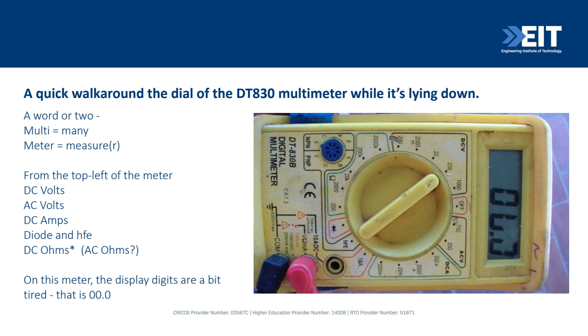While we're still on this one, if you look at the actual display here, you'd think, what are these funny symbols? It looks like an L and some other symbol. Those segments have died on this meter. I have a good feel for what they are, so if I see that segment missing and the other 6 are in place, I'm pretty sure that's either a 0 if we put that one in, or it's an 8 if we replace that one and that one. But I know the middle segment, segment G, isn't missing, it's working, so I know it's a 0. But this is my own meter - if you bought one from the shop like this, you'd want to take it back and say it's missing something.